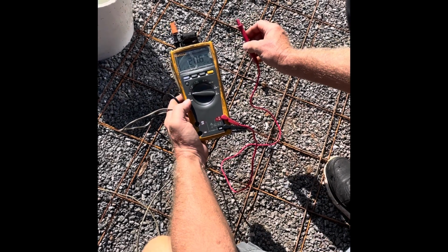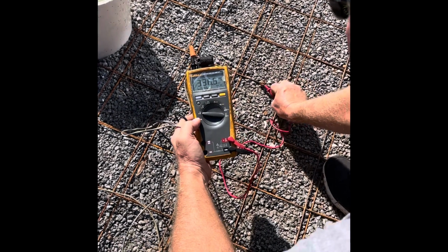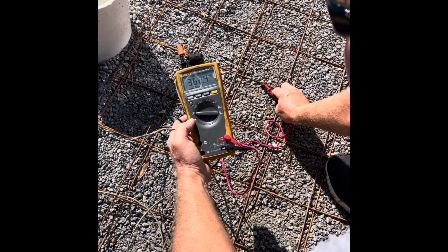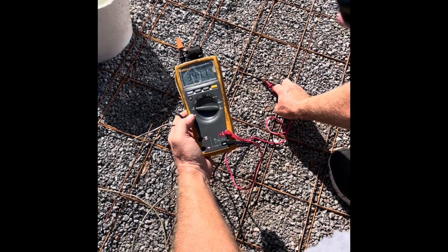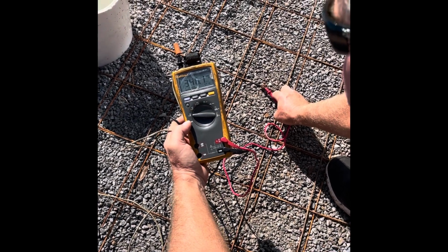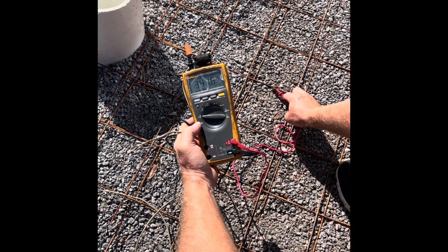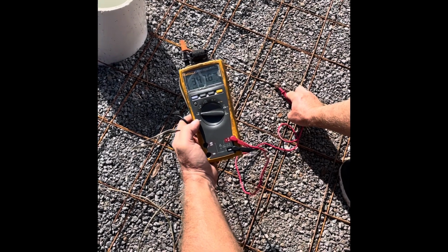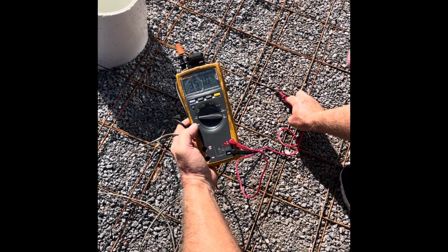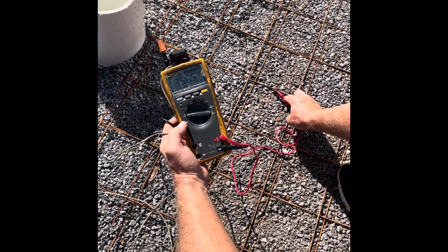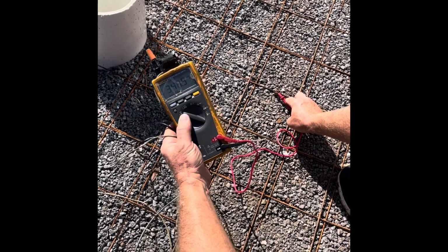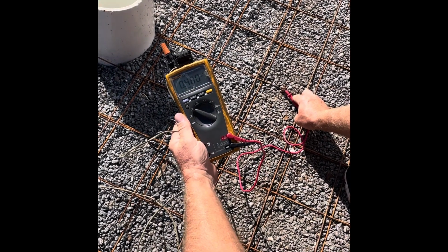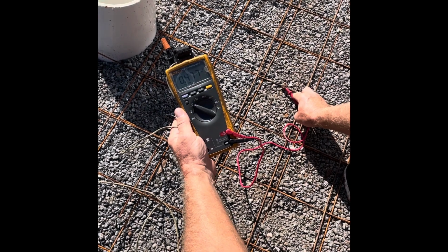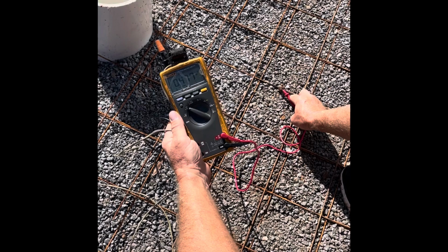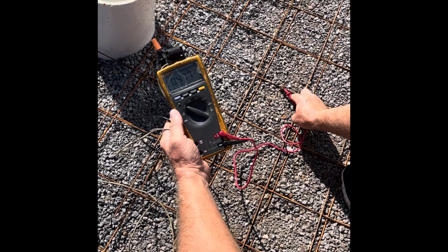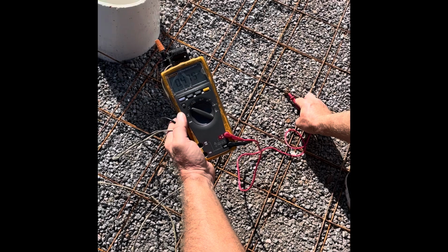All right, so we're going to start out going to this first one, and you're going to see what we have is this number that constantly moves. It'll go up and down with any variation of the load that's on the power company's system. If we switch over to DC, we're going to see a number that settles in pretty quick, and that we find to be fairly consistent around pools that seem to be bonded correctly.